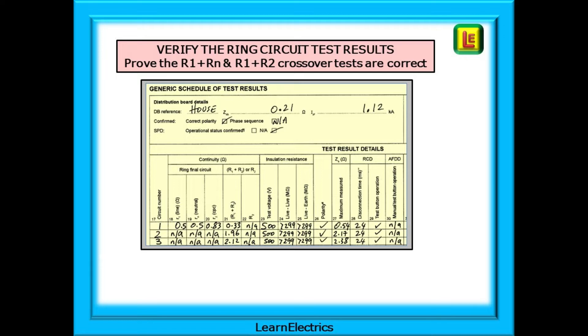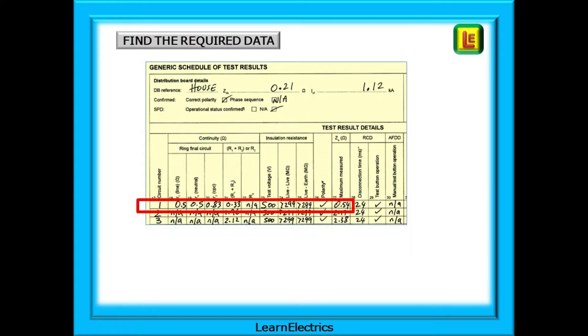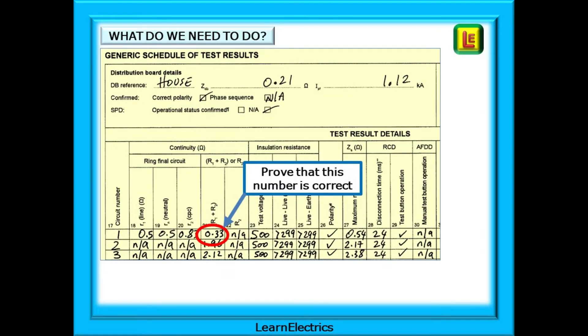We want to verify the ring circuit test results. Can we prove that the R1 plus R2 crossover tests are correct and the results are valid? Shown here is a copy of the schedule of test results, the sheet that lists the test result details. We need to find the required data for the ring circuit, which happens to be circuit number 1. This data has been highlighted by the red box.